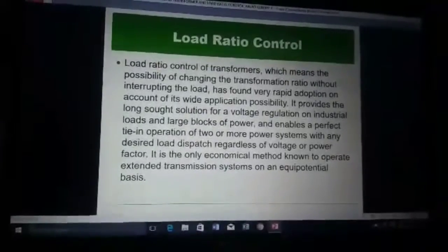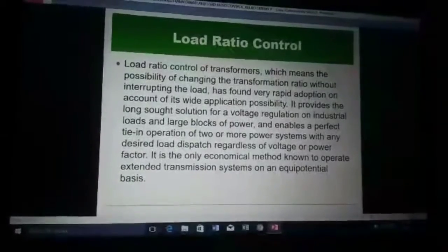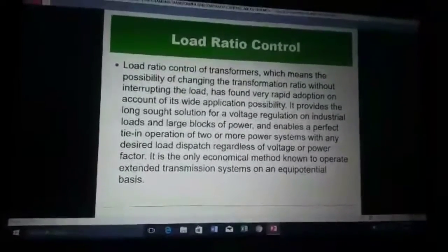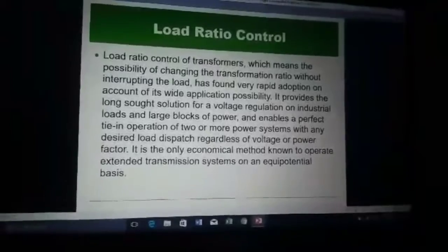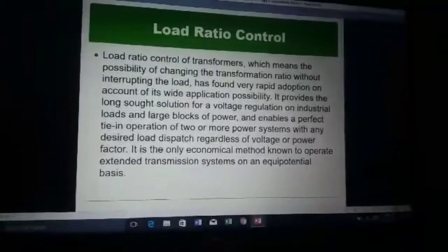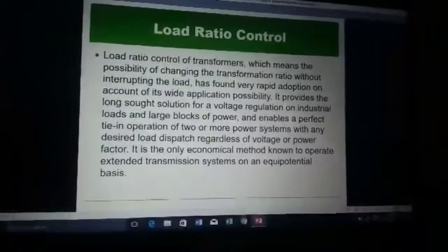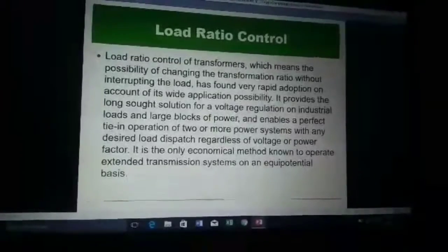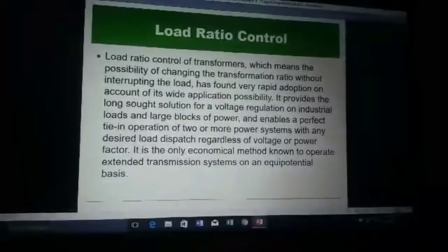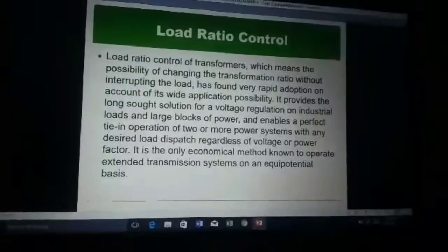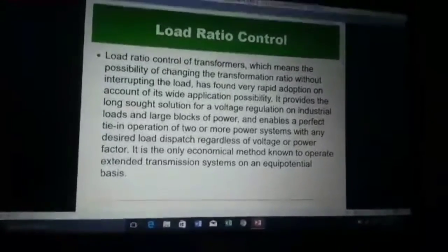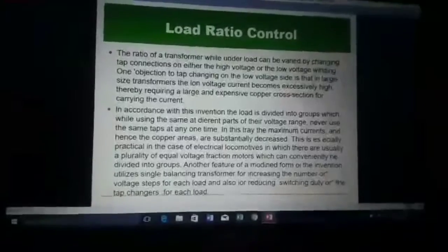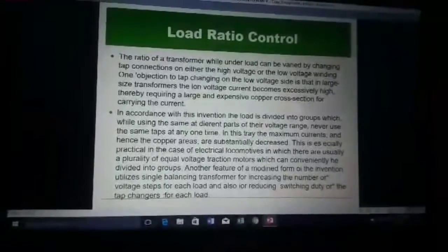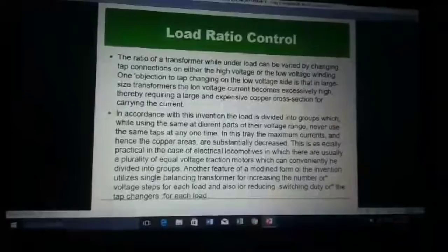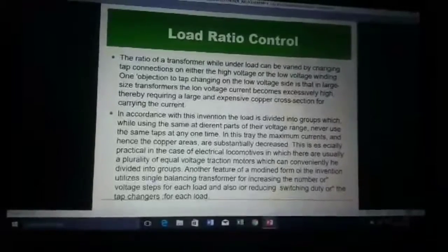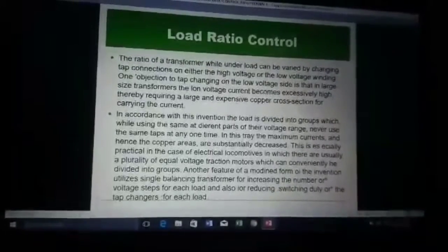Saka sinasabi dito na equipotential basis. So, sinabi na equipotential basis. So, ito yung, from the word itself, yung mga equipment na may kakayanan or mga possible na maging part ng transmission system na provide ng mga loads. So, the ratio of a transformer while under load can be varied by changing tap connection on either the high voltage or the low voltage winding.